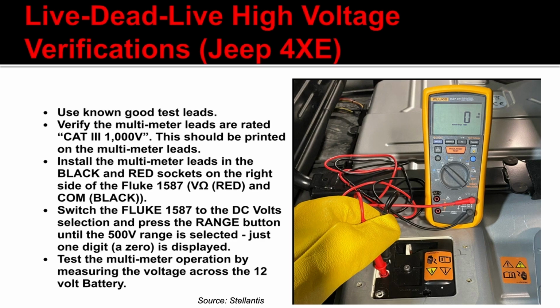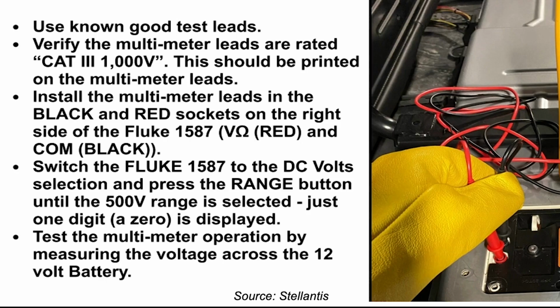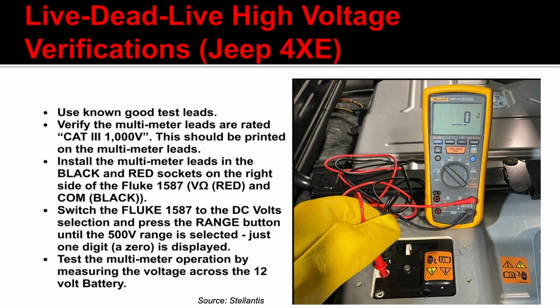If you used a battery proving unit, like the Fluke PRV 240, or a wall socket or a 12 volt battery, whatever you want to use, make sure your meter is connected correctly and you're not having a bad day misreading your meter. You want to do the live, hey I got a circuit, then the dead, this is dead right here, and then back to live again. That's what we did here.